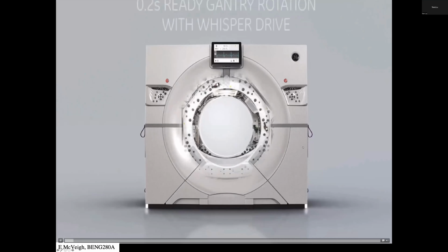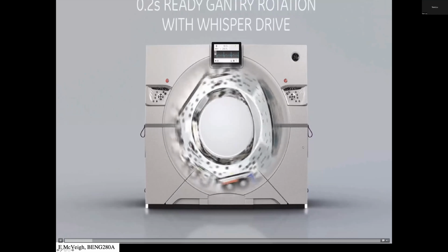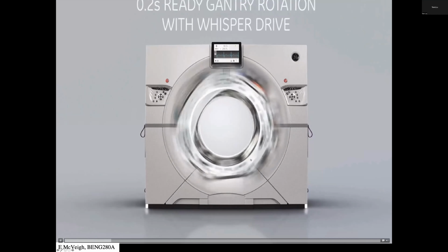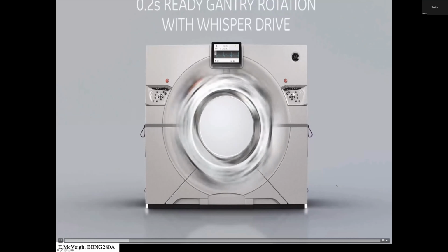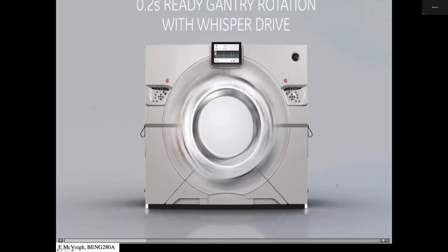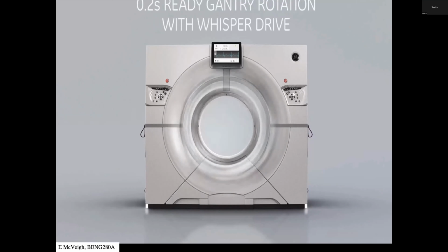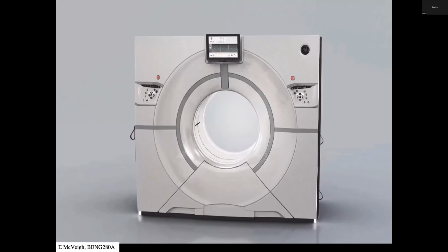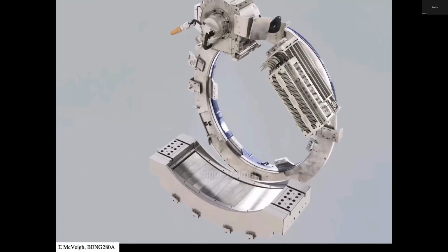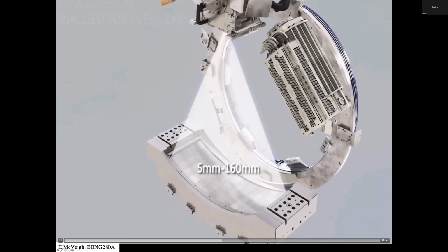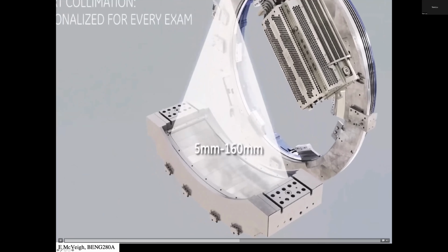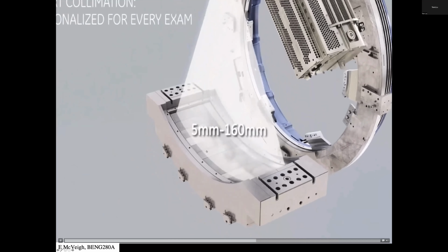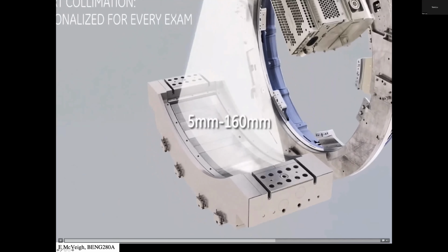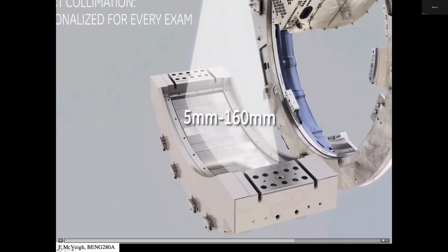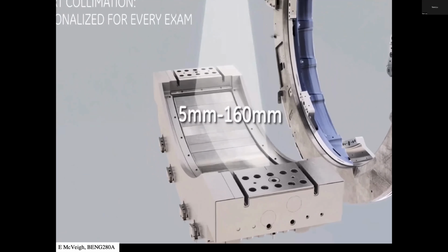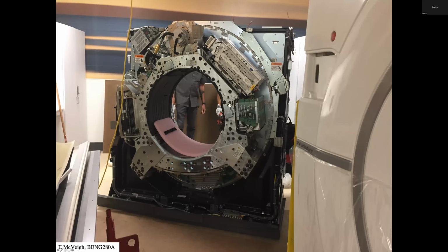So this is a modern CT scanner. This is what we have over in the Thornton Hospital. And, you know, this video is working. That's kind of what it looks like if you could see through the skins. It rotates once, 360 degrees, every 280 milliseconds. That's going to go down to 230 milliseconds soon. This is the detector array inside, and there's the X-ray tube there. And so ours is 256 detectors this way and about 1,000 detectors this way. Right? And that's what it looked like when they were putting it together.